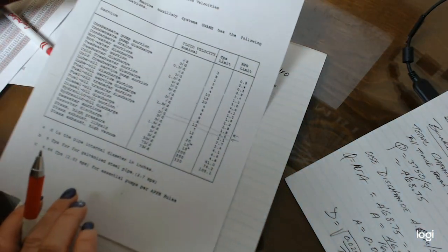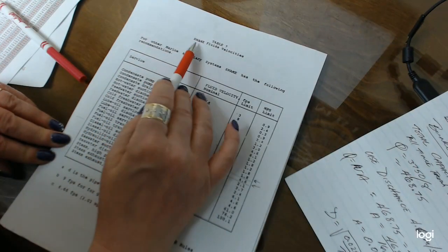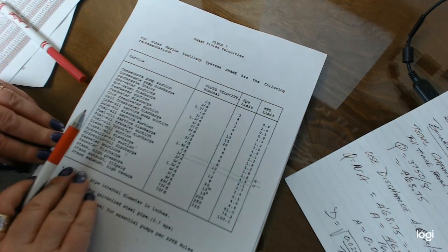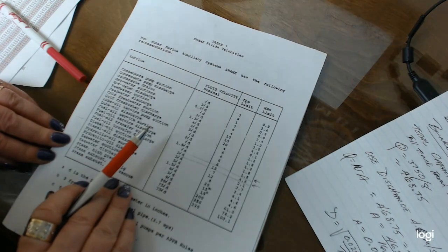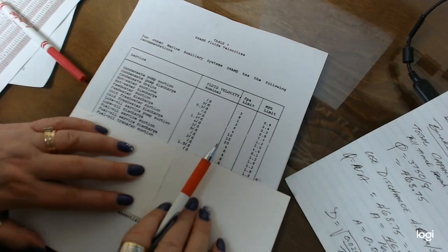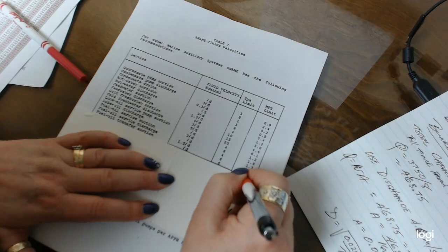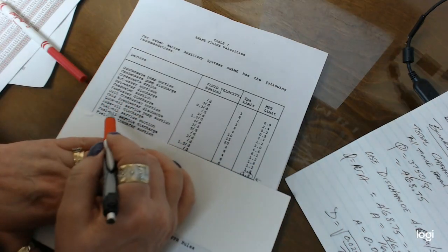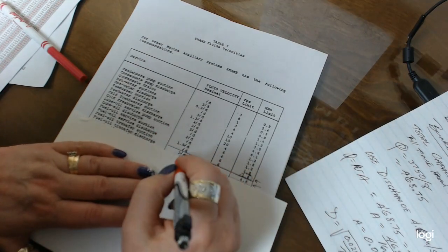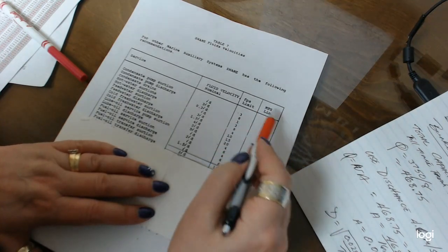On your D2L page, you will find a sheet like this that is available, and this is called the SNAME Fluids for Velocities. This is taken out of the marine engineering book, but I've put it online for you guys. So in my case, what I'm doing is I'm looking for fuel oil transfer suction. So I'm going to just draw a line across here. I'm using this number because in this particular setup, fuel oil is HFO. I'm also looking at transfer. So it's giving me these two numbers, 1.8 and 4.6 meters per second.